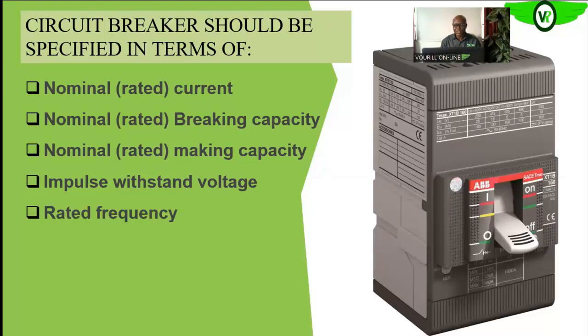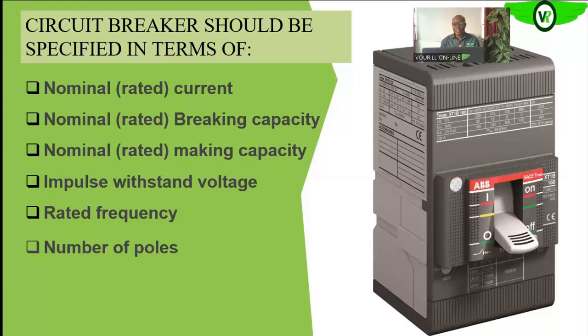Then there is the rated frequency — the operating frequency of that circuit breaker, whether it is 50 Hz or 60 Hz — which you will see clearly on the nameplate. And of course, the number of poles. In a three-phase distribution system you will need a four-pole breaker: line one, line two, line three, and neutral. But if you are supplying a three-phase load directly, or in a medium or high voltage environment, a three-pole circuit breaker will be needed.